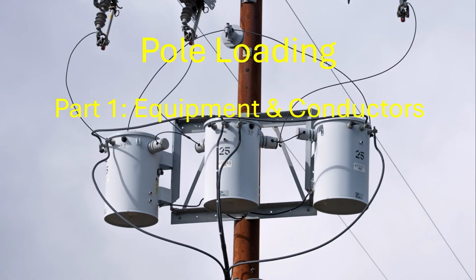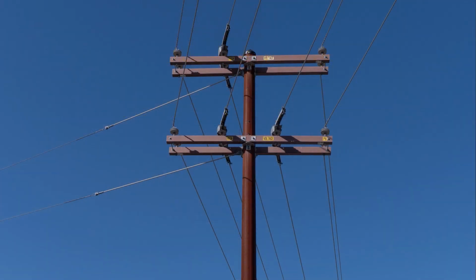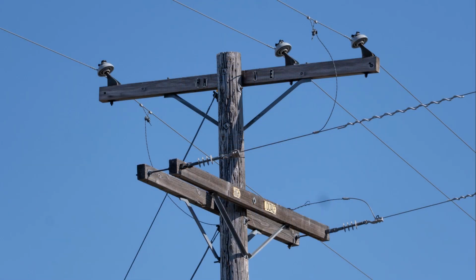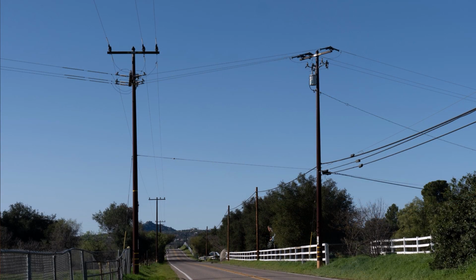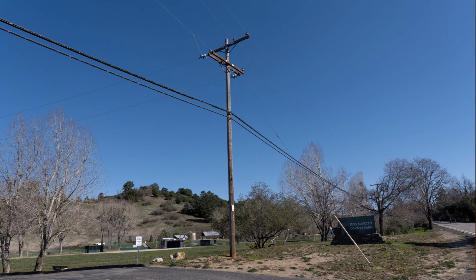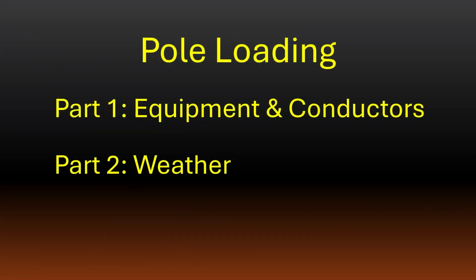We'll also cover the loads that conductors place on poles in 3 different configurations, including tangent poles, angles, and dead ends. Understanding some basic concepts and terminology of pole modeling is critical to designing an overhead line that can withstand the heavy physical loads of the equipment and extreme changes in the weather. Part 2 will cover additional pole loading concepts due to weather.